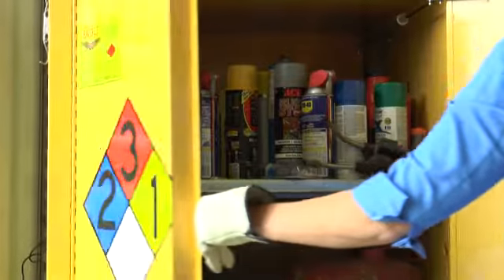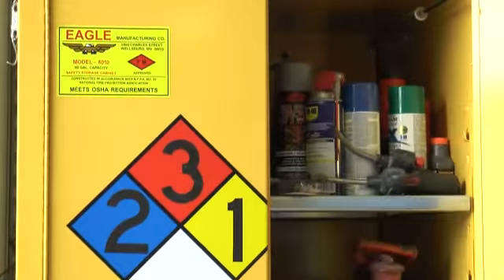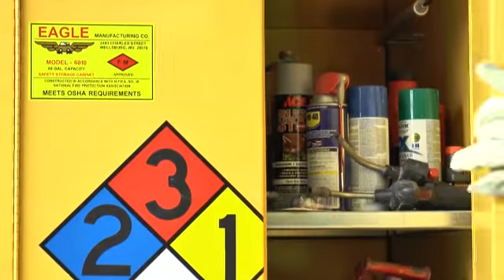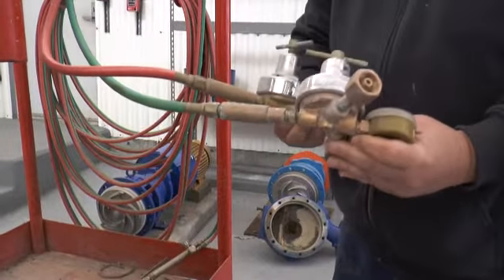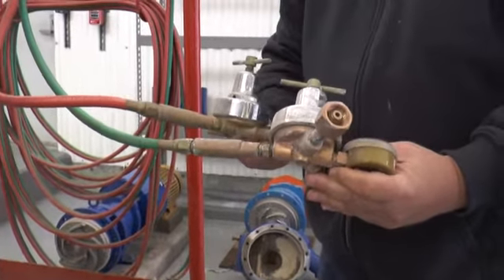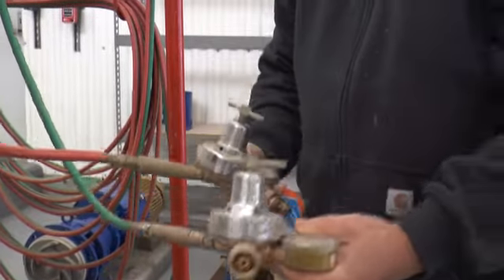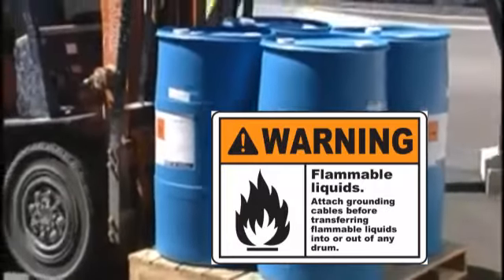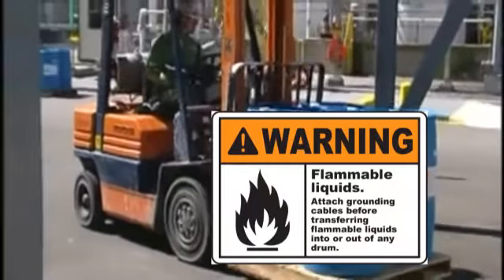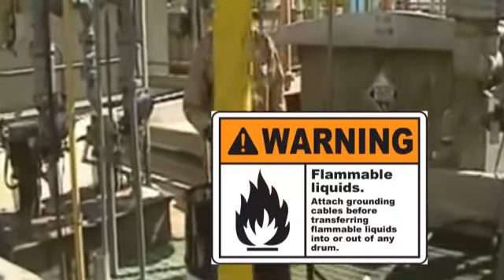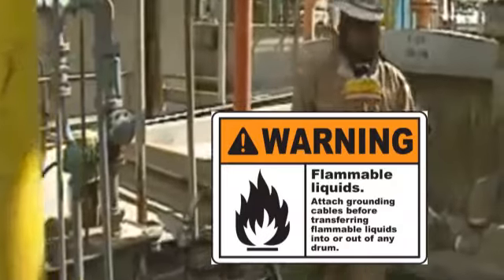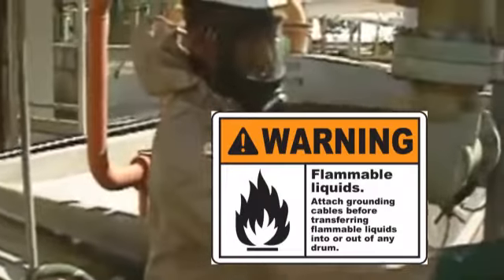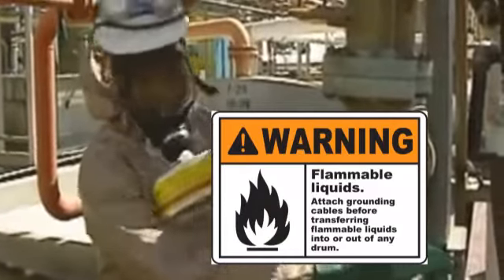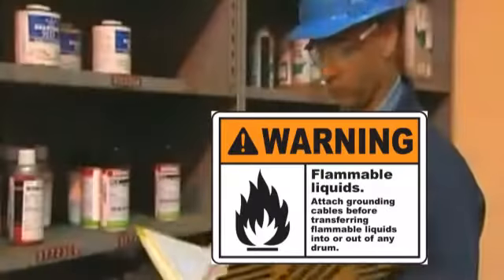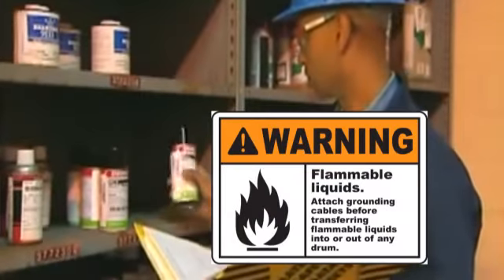Flammable liquids must be stored in the manufacturer's original container or in approved safety cans equipped with a flame arrestor and self-closing valve. During transfer from one container to another, containers of flammable and combustible liquids must be grounded and bonded. This requires that each container be set on the ground and directly contact each other during transfer. Dispensing containers must be equipped with a self-closing valve or other device to minimize potential for spills.